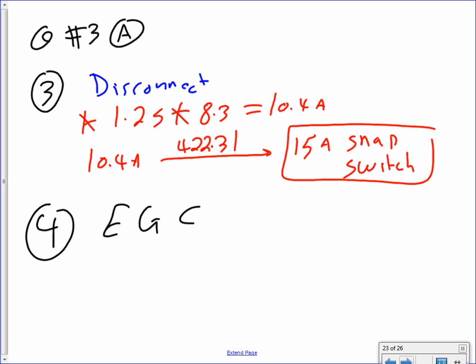15 amp snap switch. What is the snap switch? You're looking at it right here. So, 15 amp snap switch. Right? That's a 15 amp snap switch. Because if you guys go to 422.31, it will tell you you can use the snap switches to disconnect the garbage disposal. Your plug can also be a disconnect.